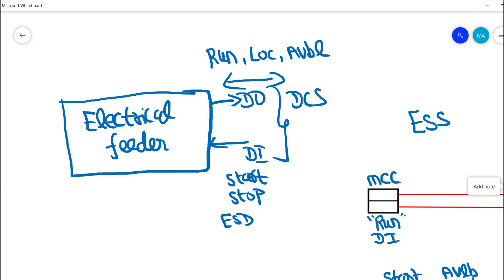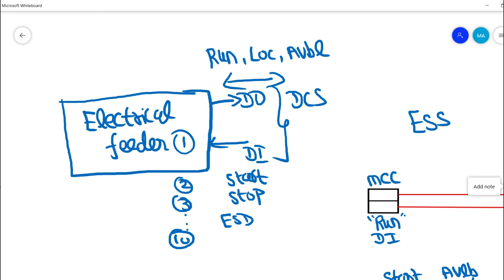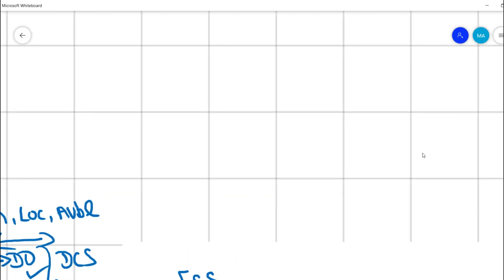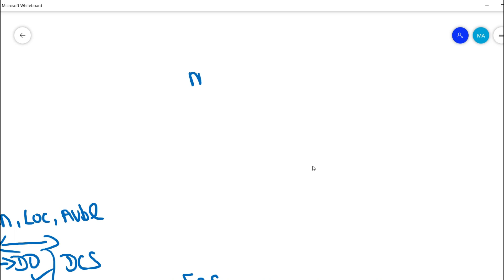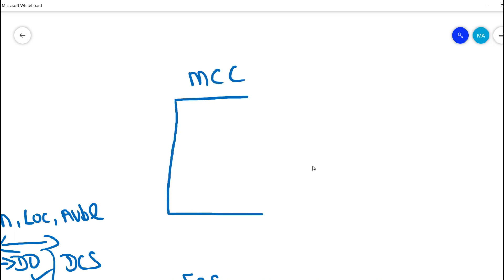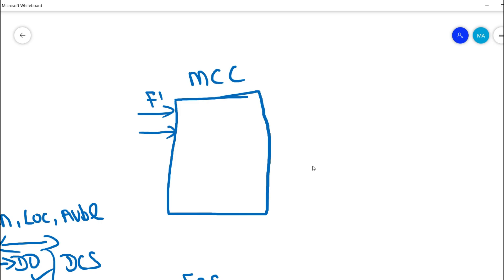These signals run from the electrical feeders to DCS. In a substation we would have many electrical feeders — for example around 10 electrical feeders — and all their control supply signals would be routed into an electrical instrument interface panel, which is the MCC (motor control center). Feeder one and feeder two control signals come in, and similarly all 10 feeders terminate into this motor control center.